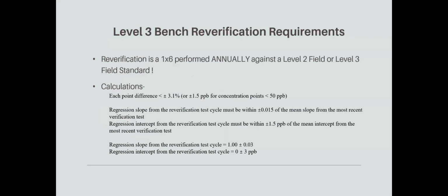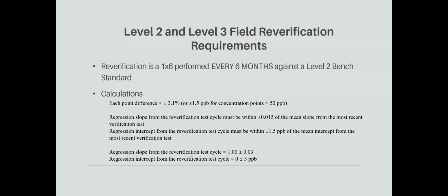For level 3 bench re-verification, this only needs to be performed annually, and it can be, like I said, performed against a level 2 field or level 3 field standard. Most of the calculations are essentially the same. For level 2 and level 3 field re-verifications, they're performed every 6 months against a level 2 bench. And again, those calculations are all the same.